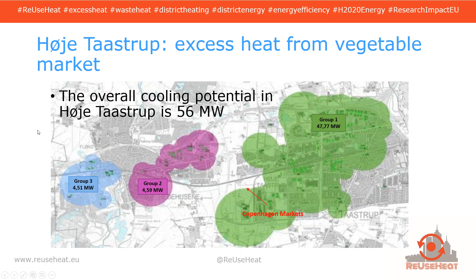So to sum up the facts about this case, the total floor area in the market is 15,000 square meters. And of course, there is a cooling capacity, which is 2 megawatts, and a heating capacity, which is 2.3 megawatts. And this operates with COPs of around 2.2 for the refrigeration unit and 3.2 for the heat pump COP on the heat side. And the total investment was approximately 3.4 million euros. And currently, the heat pump can contribute just 3% of the total heat consumed in the area of Høje Taastrup. But you can say that it is a very cheap form of energy to use, a good potential to be developed even further in the area.